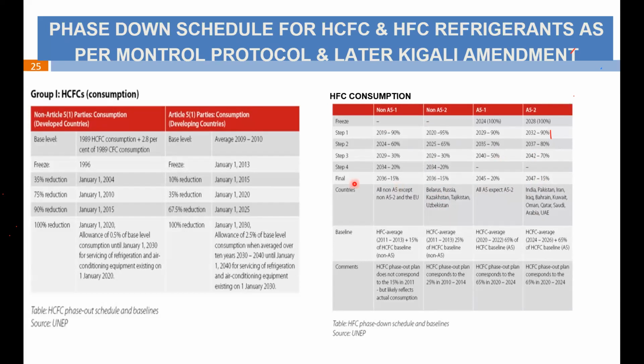So if you see the final phase out date for HFC refrigerant, it is 15% for developed countries in 2036. That is, they have to bring down the consumption to 15% of the base value, which is already defined. In our case, this is 2047, but this has to be done in 4 steps. By 2032, we have to achieve 90% of the base value, so we have to reduce by 10%, and by 2047 we have to come to 15% level of the base value. So we have to reduce by 85%.